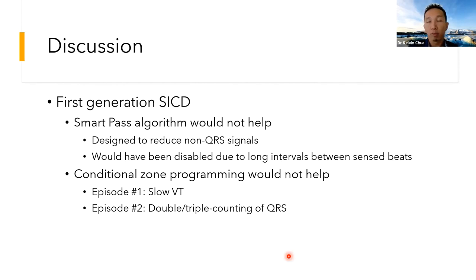With regards to the earlier mentioned first generation SICD did not have the smart pass algorithm, but actually, if you think about it, the smart pass algorithm would not have helped. The smart pass algorithm is designed to reduce non-QRS signals, and it would also have been disabled due to long intervals between sense beats. This is part of the SICD's algorithm to reduce the chance that under-sensing may lead to inappropriate lack of detection of important arrhythmic events. Also, the conditional zone programming would not have helped. This was a very slow VT.